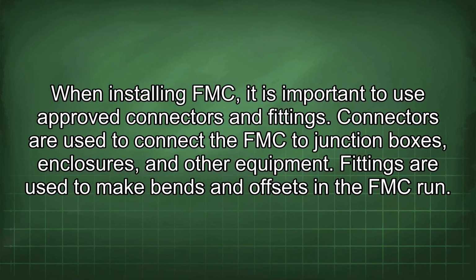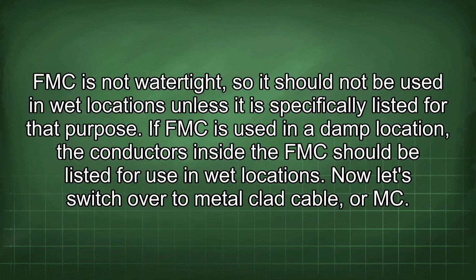When installing FMC, it is important to use approved connectors and fittings. Connectors are used to connect the FMC to junction boxes, enclosures, and other equipment. Fittings are used to make bends and offsets in the FMC run. FMC is not watertight, so it should not be used in wet locations unless it is specifically listed for that purpose. If FMC is used in a damp location, the conductors inside the FMC should be listed for use in wet locations. Now let's switch over to metal-clad cable, or MC.